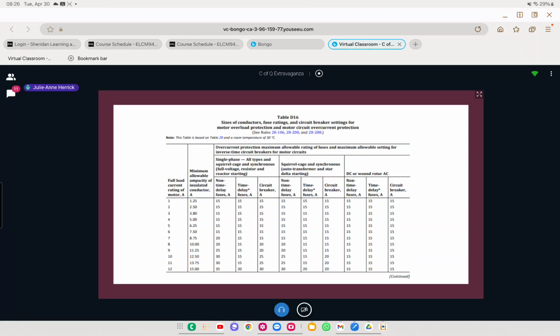D16 used to be table 28. It is not table 28. Apparently, they decided to bury it down in Appendix D. D16 does all your motor math for you. So over here, you see your FLA, full load current rating of the motor, minimum allowable ampacity of insulated conductor based on continuous duty. And we have non-time delay fuse, time delay fuse, and circuit breaker.